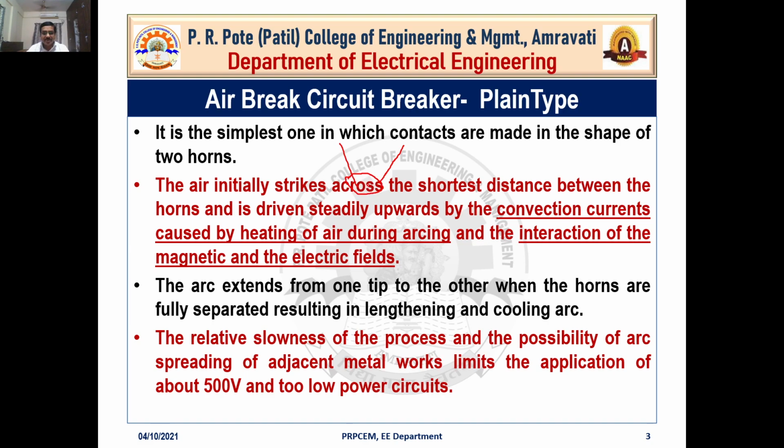Initially the arc is formed there when the moving contact starts parting from the fixed contact. That way the arc is initiated, and this arc is elongated in the upward direction, with the help of the air which we are initiating, so that the arc will be moving in upward directions.